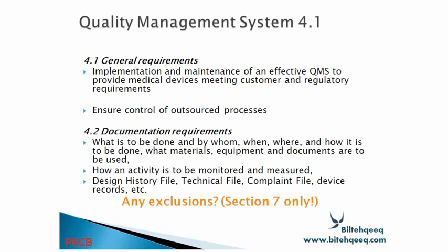And 4.2, documentation requirements: what is to be done and by whom, when, where and how it is to be done, what materials, equipment and documents are to be used, how an activity is to be monitored and measured, design history file, technical file, complaint file, device record, and any exclusion. If there is any exclusion, we also have to describe this exclusion. So we have to develop proper documentation procedures: who is responsible for what and who is doing what.